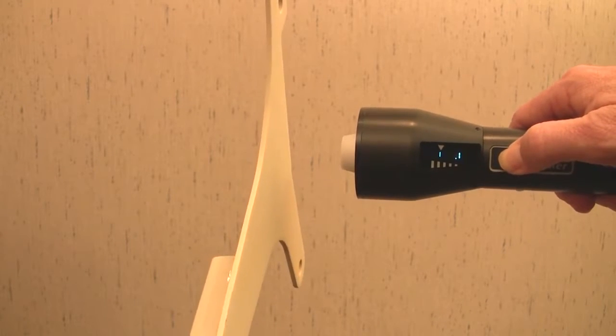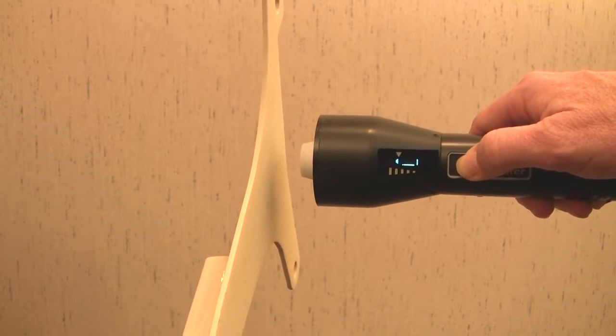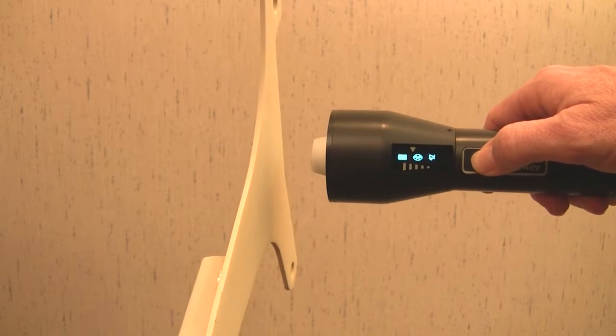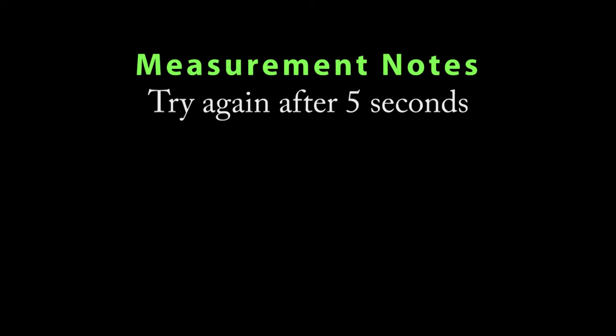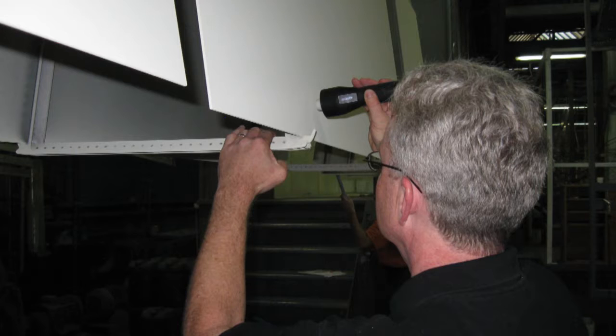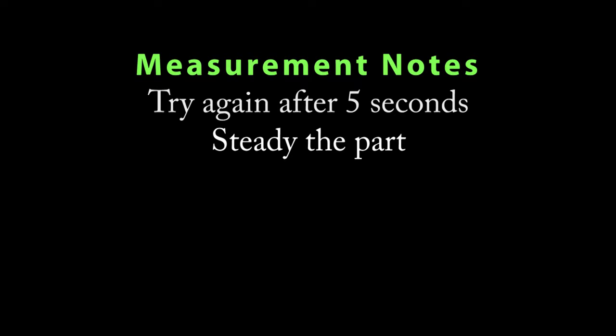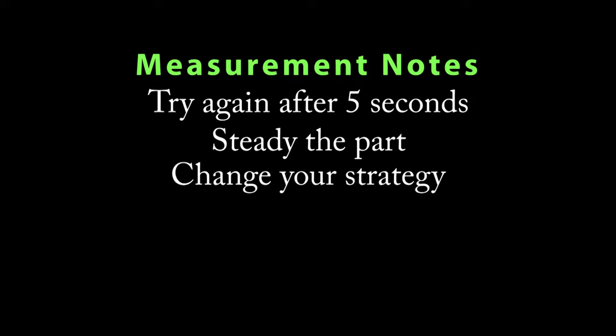Wait 1 or 2 seconds between measurements. Poor probe orientation will lengthen the measurement time or result in no thickness prediction at all. If a thickness result does not appear after 5 seconds, release the check button and try again. Small, erratically swinging parts may present measurement challenges. Steady the part whenever possible. If erroneous readings continually result, change the measurement strategy by rotating the probe, altering its alignment to the part, or by measuring a different location on the part.